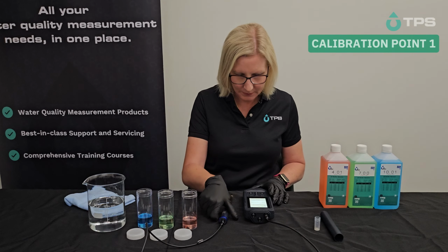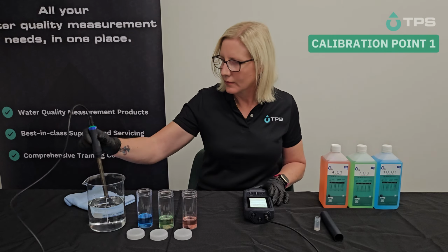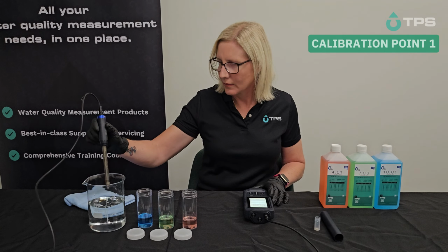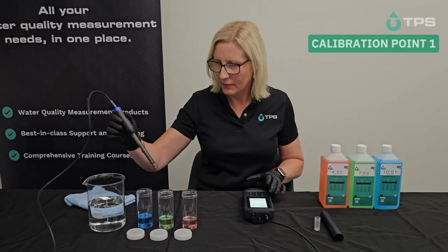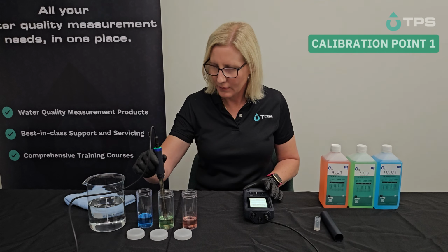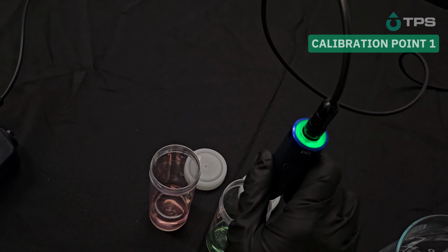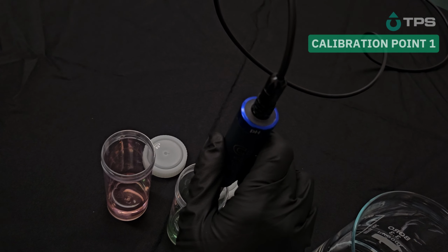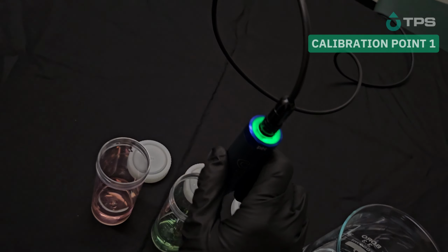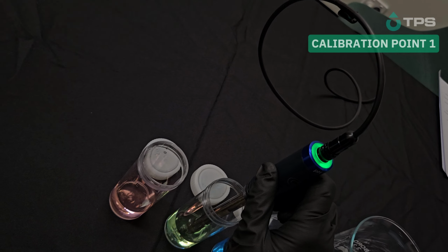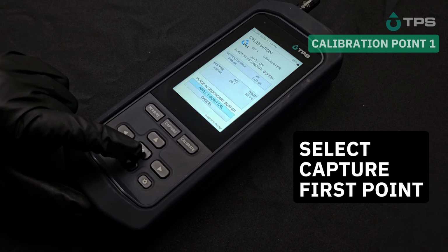Rinse the sensor tip thoroughly with deionized water and gently shake off the excess. Immerse the sensor tip into the sample jar containing your primary buffer. Gently stir while keeping the tip submerged. Wait for the sensor's stability indicator, LED, to turn solid green, indicating a stable reading. Select Capture First Point.